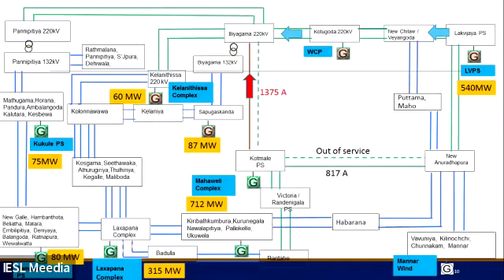So what happens? A single circuit tripped. Then that load transferred to circuit number 2, which is 1,375 amperes. The overcurrent setting of this circuit is 1,500, which is above 1,375, so we maintained the N-1 contingency criterion even under the hydro Mahaweli maximum condition.